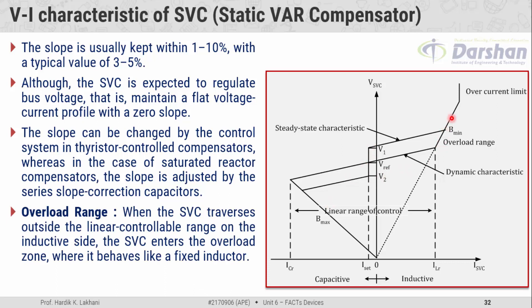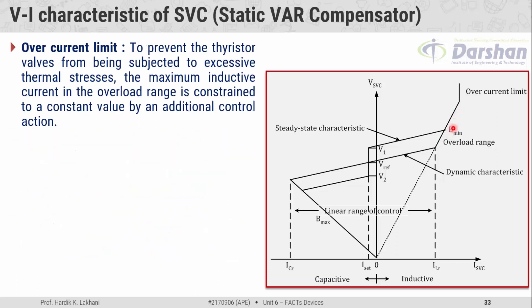The overload range is the portion of the characteristic defined when the SVC traverses outside the linear controllable range on the inductive side. When the SVC goes beyond this line on the inductive side, it is said that the SVC enters into the overload zone, where the compensator behaves like a fixed inductor. In this region, we can no longer change the impedance offered by the SVC for compensation purposes.